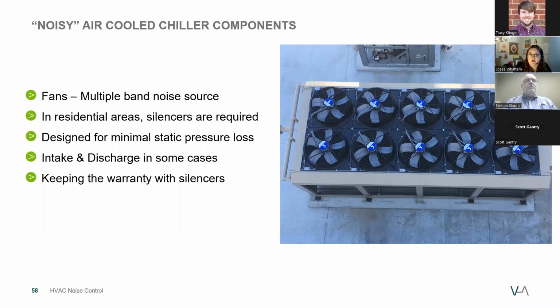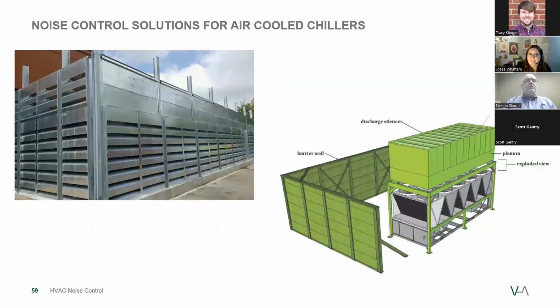So coming up next are some photos of installed solutions. Here's a sketch and the installation photo of an acoustical barrier and discharge silencers. You can see the steel base around the equipment to support the discharge silencer bank. So no weight loading of the silencer bank is on the unit itself. Additionally, the barrier wall is self-supporting and has acoustical louvers to attenuate any inlet air.